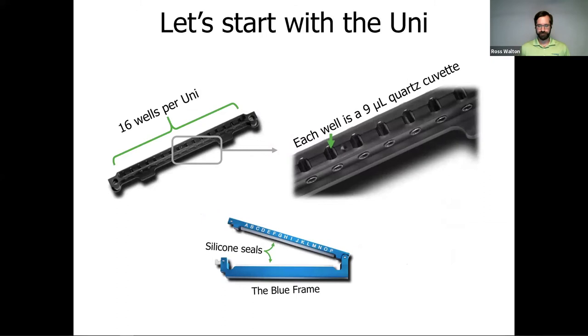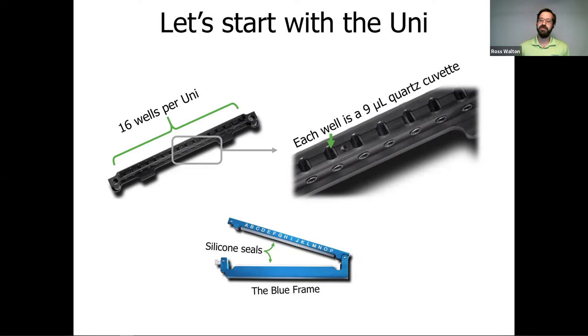UNCLE uses a unique sample holder called the UNI. A UNI contains 16 wells that are actually 9-microliter quartz cuvettes. You can use anywhere from one to all 16 of these wells during an experiment. Before an experiment, the UNI is clamped between two silicone gaskets, sealing either end, and held within a blue frame. This keeps your sample safe and secure during the experiment, and is what gives you the high throughput and low volumes that are so important for AAV stability work.